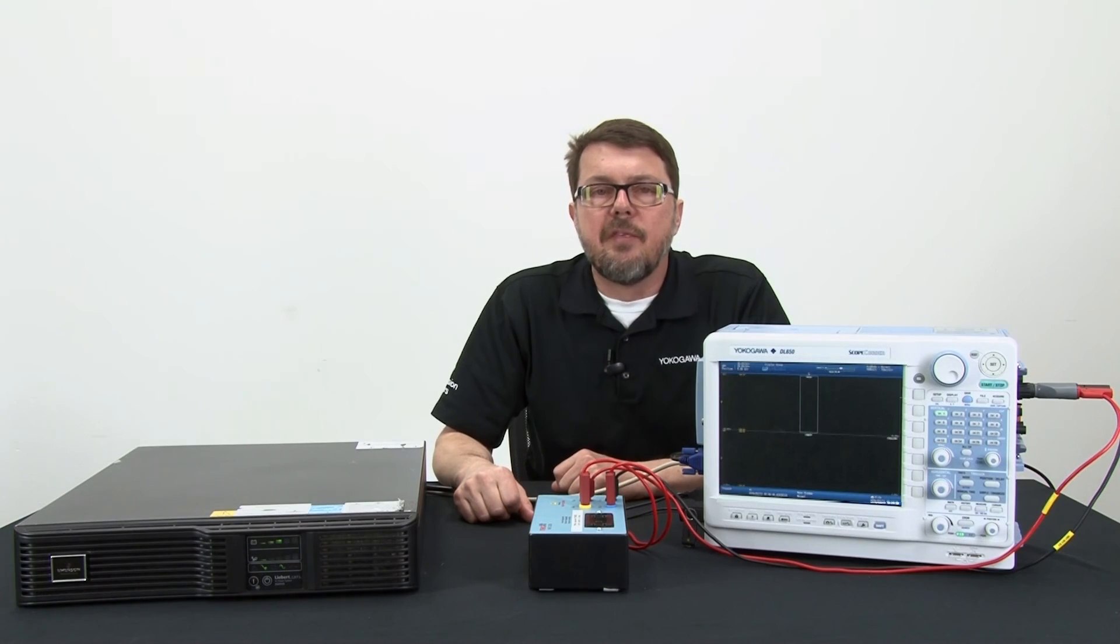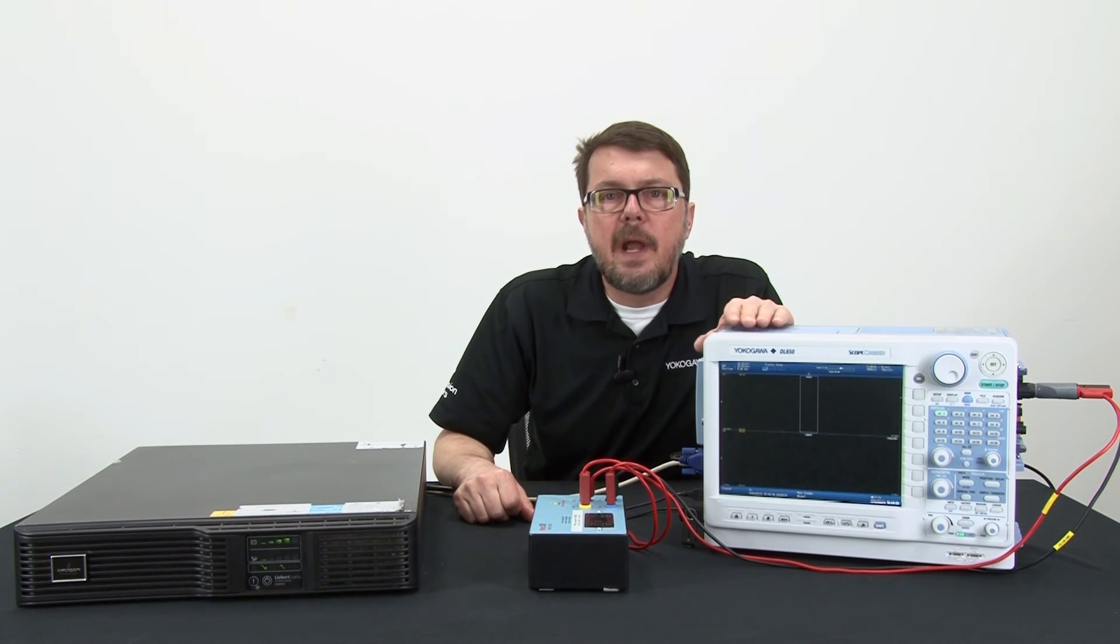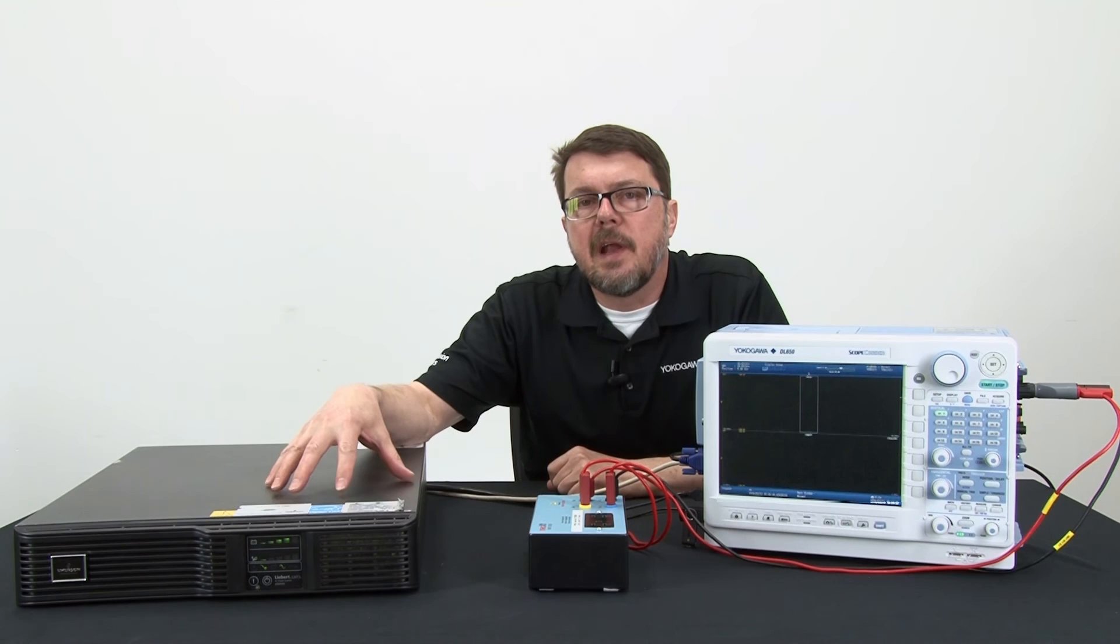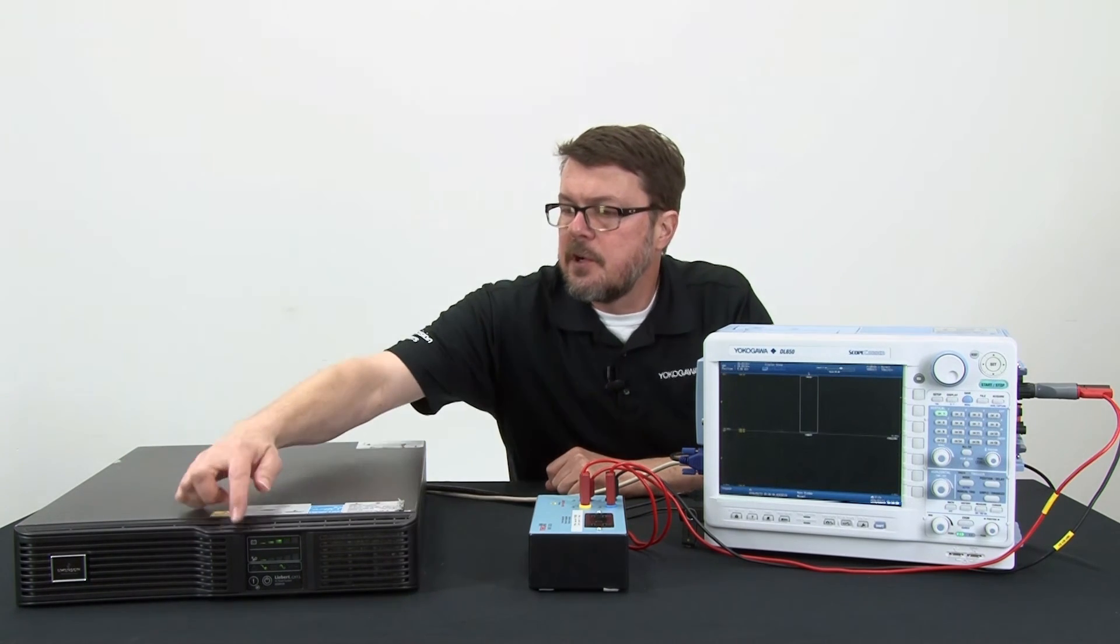Now I'm ready to run the test. The scope trigger is armed and waiting. All I have to do is force the UPS to switch over to its internal battery and inverter. This will simulate the grid dropping out. Here we go.